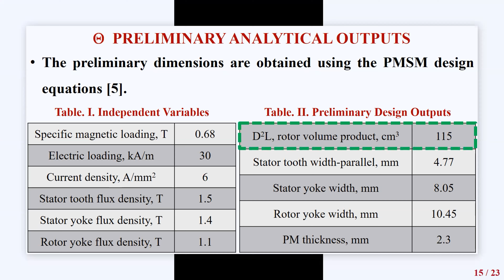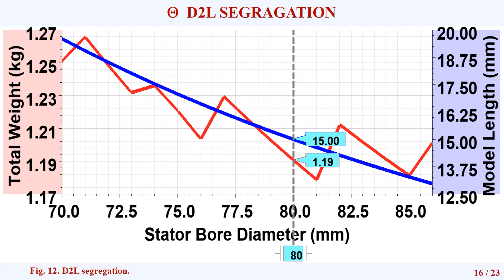The weight, as we review the figure, decreases as the model length decreases, as shown in figure 12. However, a shorter length will cause production and winding problems. The stack length is chosen to be 50 millimeters, considering the size limitations specified in figure 9 previously, and the end span length of coils.